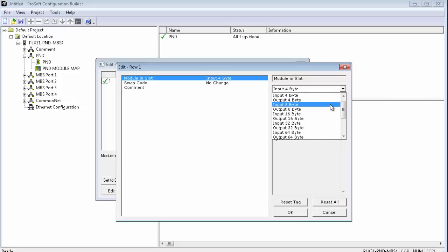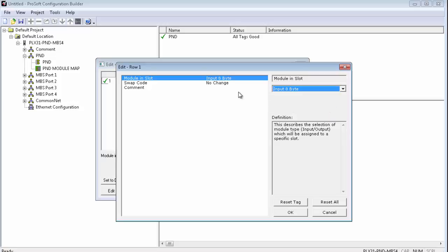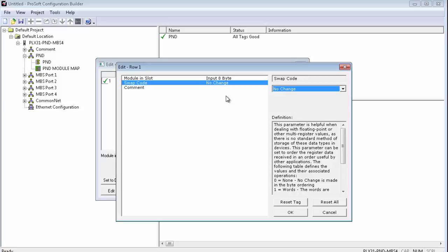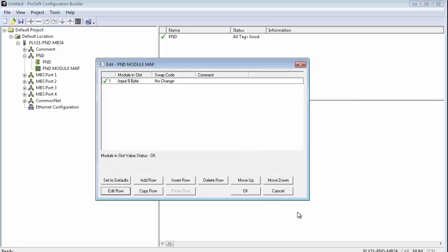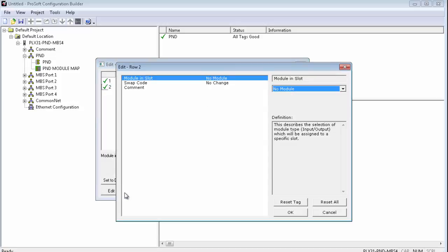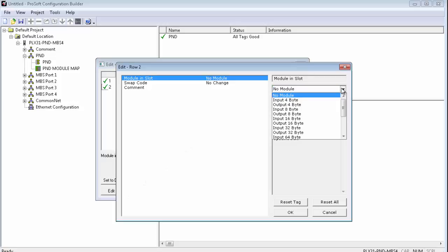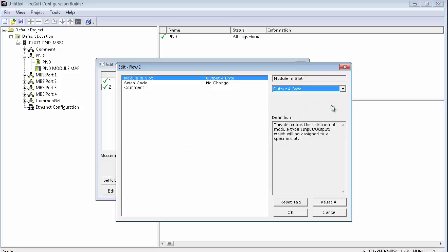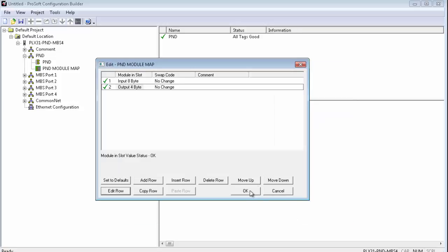Simply click on Module in Slot and from the drop-down list choose Input 4 bytes. Now, since we're going to be sending status data to the PLC as well, I'll select Input 8 bytes to accommodate that data. If you notice your bytes or words are scrambled, you might need to swap bytes or words for this particular device or data type. We can do that by using the swap code here. Once completed, click OK. Now, we'll add a second row and edit that row, this time for Output 4 bytes. And click OK. And click OK again to close the window.